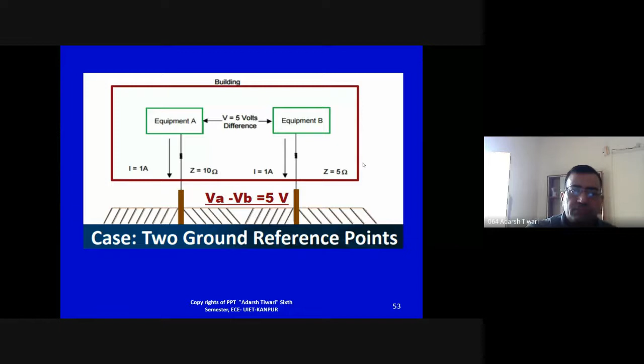Now let me touch a very important concept of step and touch potential. In power systems this is very important for safety. If there is some fault and the grounding is not proper, whenever somebody is touching that structure, that is called touch potential. And if the ground fault is there and somebody is moving, that is called step potential. We always want touch potential and step potential to be minimum for the safety of humans. There is also a common mode and differential mode of voltages.